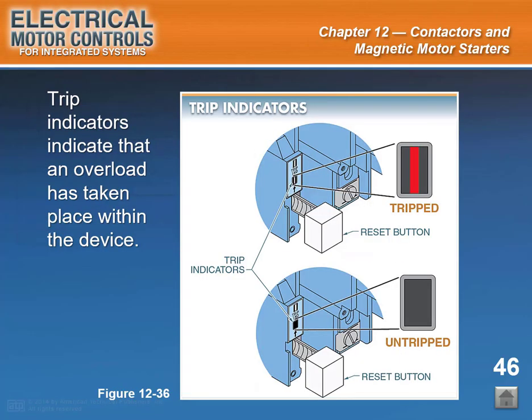Start of slide 46. Slide caption: trip indicators indicate that an overload has taken place within the device. See figure 12-36. Many overload devices have a trip indicator built into the unit to indicate to the operator that an overload has taken place within the device. A red metal indicator appears in a window located above the reset button when the overload relay has tripped. The red indicator informs the operator or electrician why the unit is not operating and that it is potentially capable of restarting with an automatic reset.